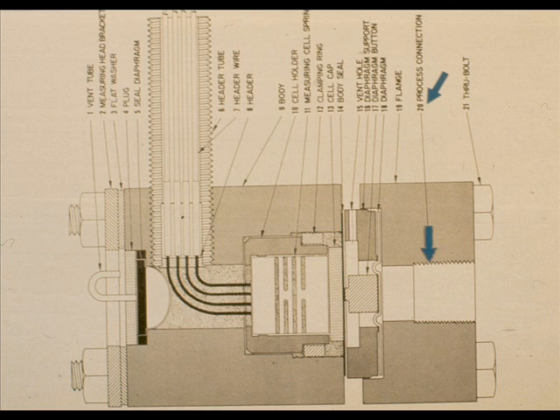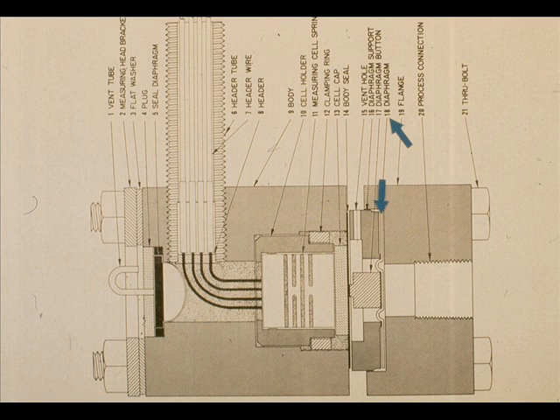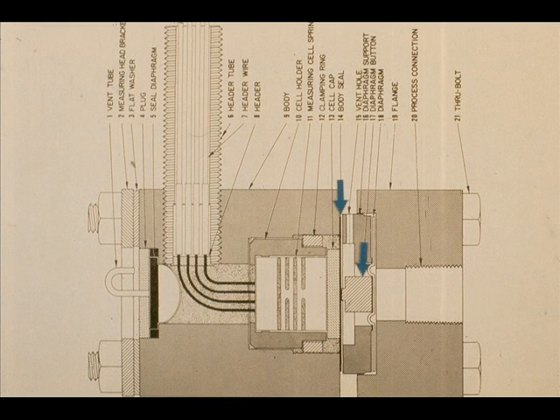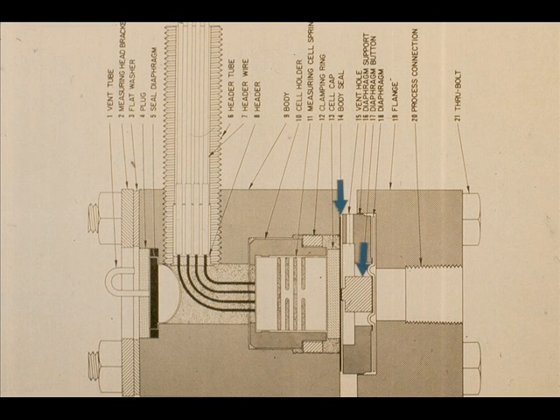In operation, process pressure enters through the process connection 20 and is applied to the measuring diaphragm 18, causing the diaphragm to move. The distance the diaphragm moves is proportional to the applied pressure.